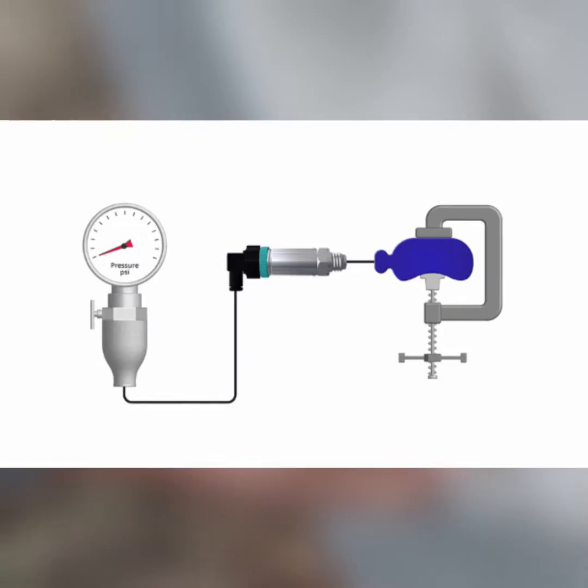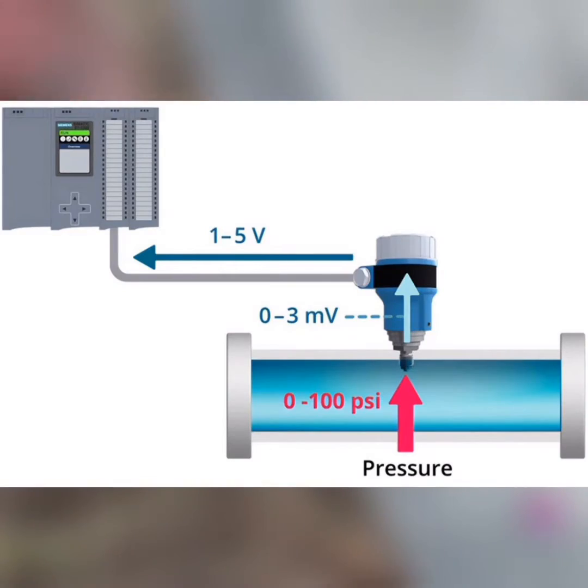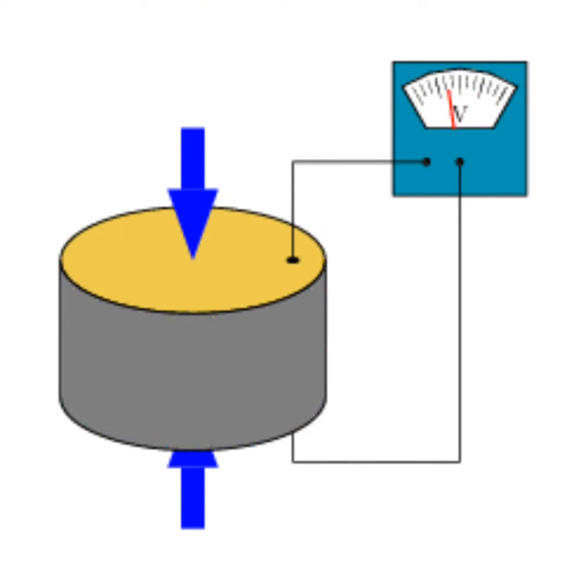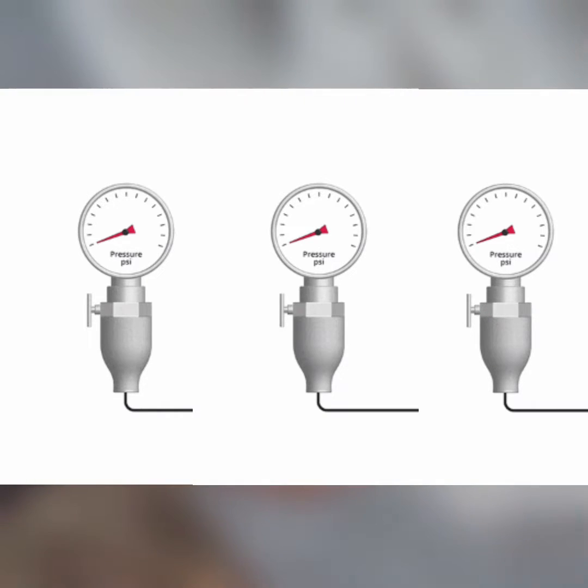Then, we have pressure transducers, also known as pressure sensors or pressure transmitters. These devices change pressure into an electrical signal. They typically use strain gauges or piezoelectric elements to measure pressure and relay the data to a control system or display.